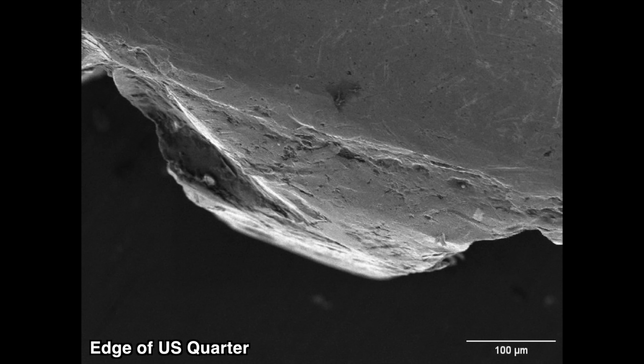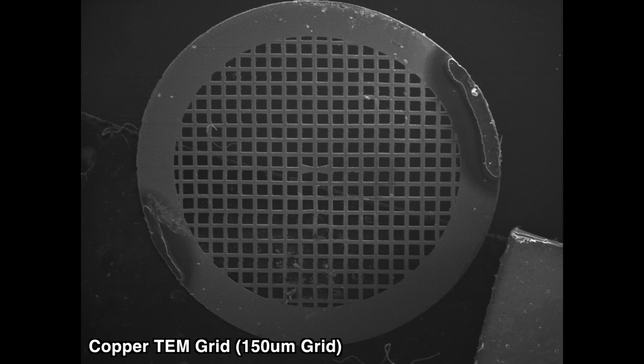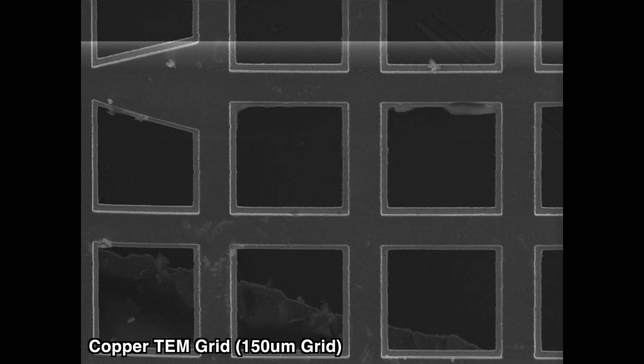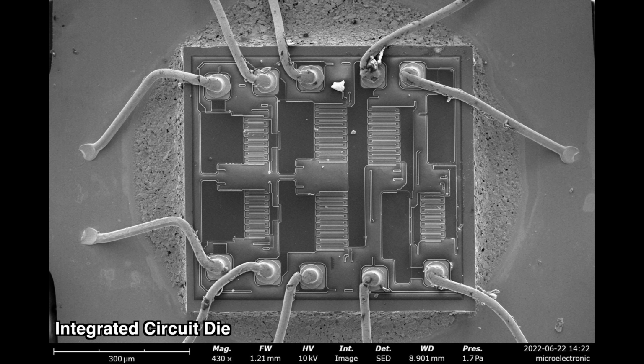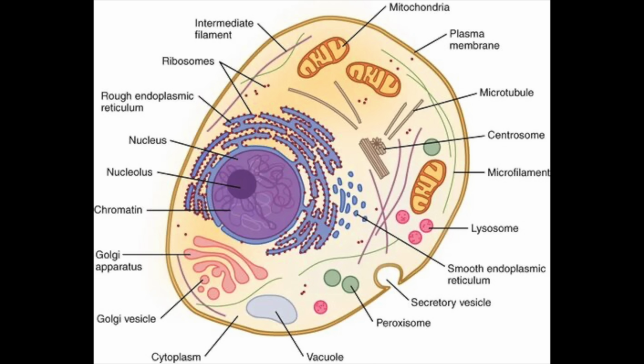Secondary electron images like this are probably the most common type of image in scanning electron microscopy. However, there is a major downside. Because secondary electrons are generated at the surface of the sample, the resulting image only contains details about the sample's surface, and tells you nothing about internal features. This makes scanning electron microscopes well suited to imaging things like integrated circuits, but poorly suited to imaging the internal structure of cells and tissues without special preparation.